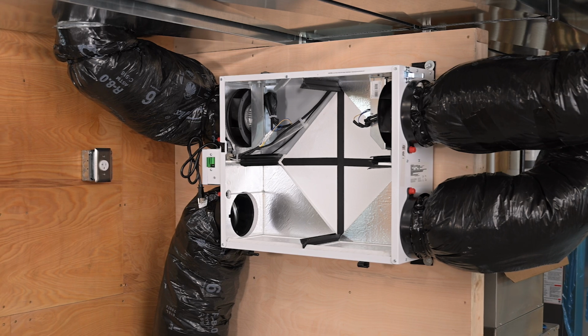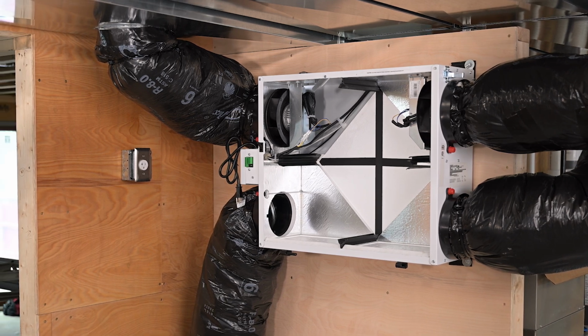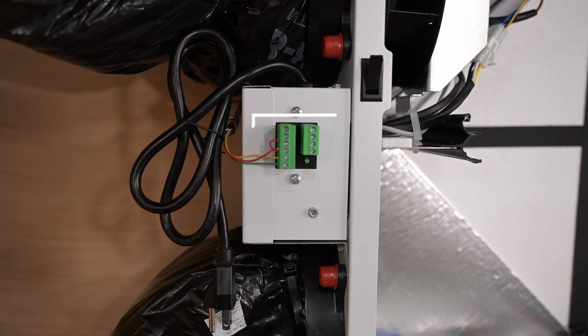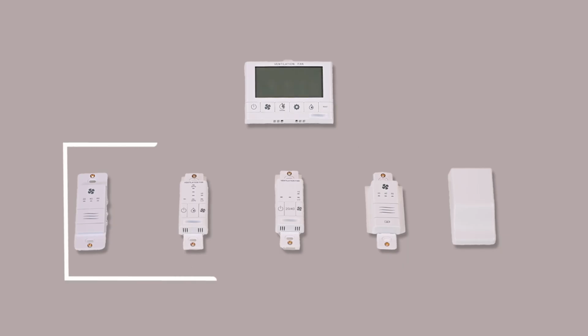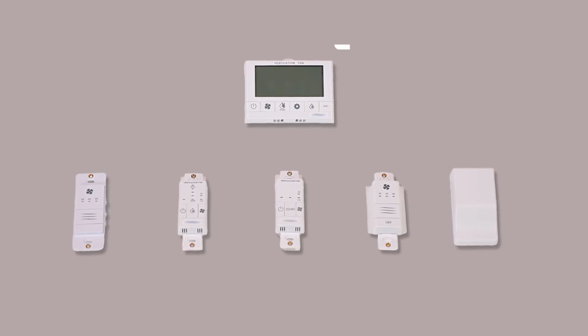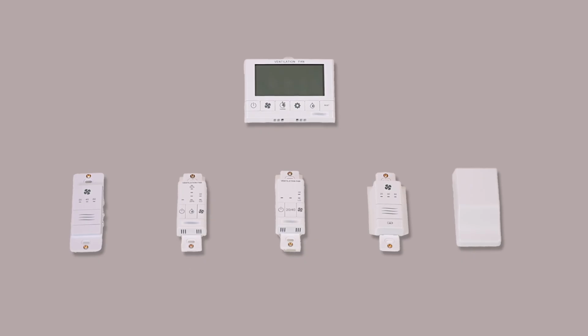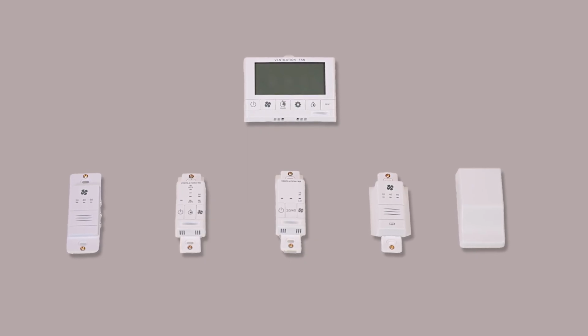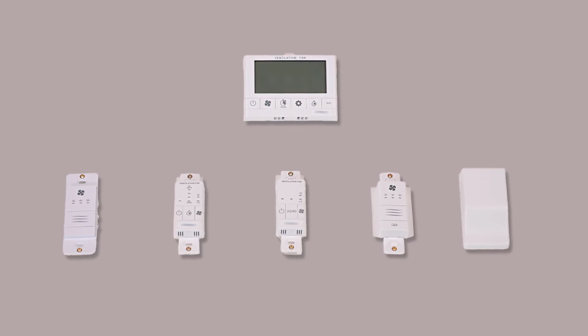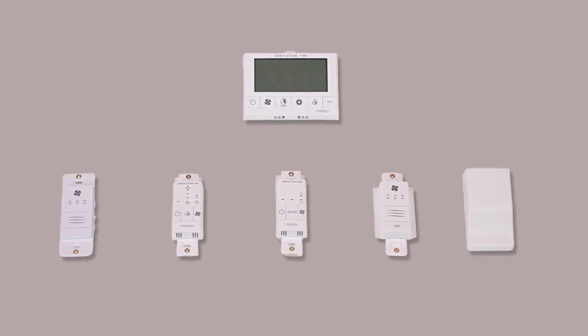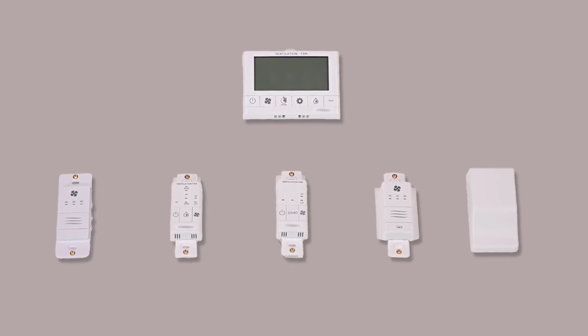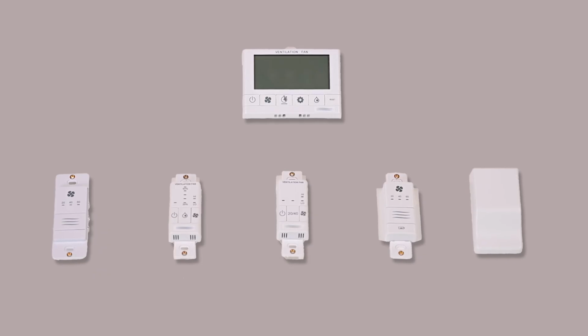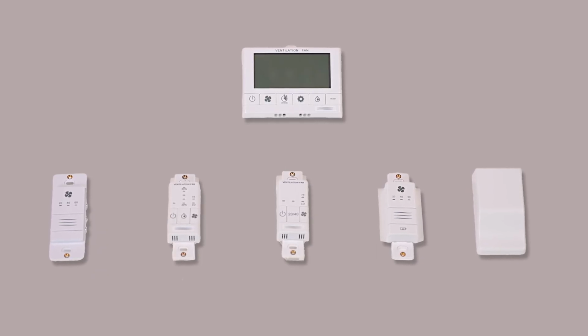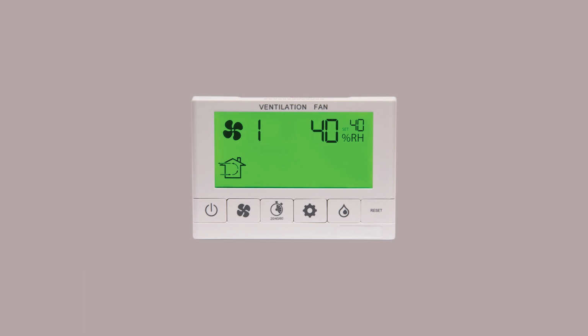Once the ductwork is connected, it's time to move on to the control and electrical connections. These units come with a 10-pin terminal block and can be controlled in multiple ways. We offer timers, 2-speed dehumidistat switches, and a precision sync wall control, which includes a convenient backlit LCD display and precision balancing to dial in exact airflow when paired with the SYNC A and F models. Refer to our controls overview for more information about the available options. You can also use any third-party control with a dry contact. In this application, we're installing the Precision Sync control.